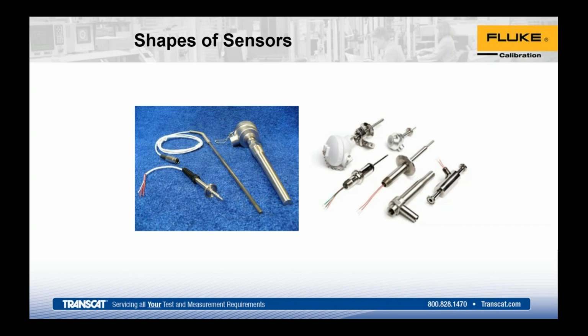The biggest thing that comes into play with the sizing is the immersion. On a standard probe like the one in the middle, there's a consideration for stem conduction, where the actual metal acts as a heat source or a heat sink, I should say, in the application. So the rule of thumb in the industry for immersion depth is typically 20 times the diameter of the stem of the probe.